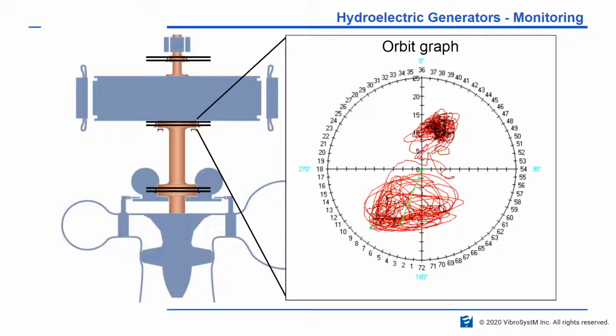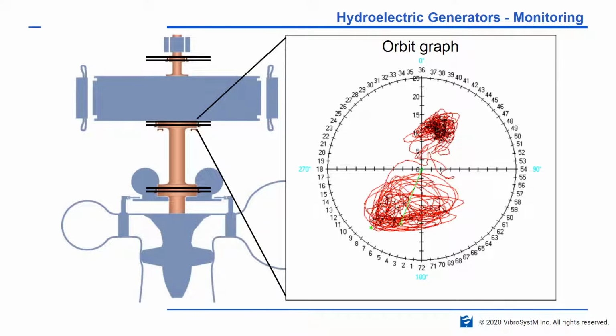So what you have on the screen is multiple rotations, and it is during a startup of a hydro generator, and we can see that prior to excitation the unit is rotating in this position, and as the field is introduced the unit moves over to this direction and then rotates. So it adopts a center in this location as opposed to this. This is what we call the mechanical center, and this is the electromagnetic center. So this tells me immediately that the air gap is uneven.